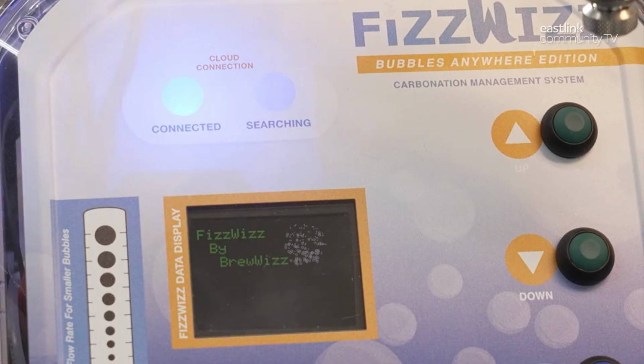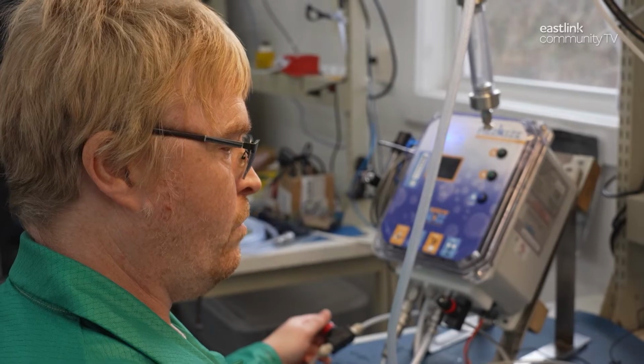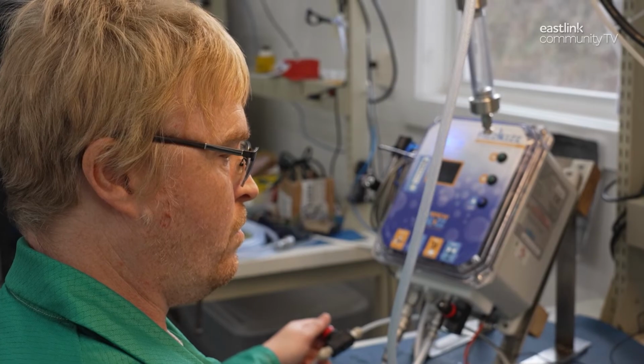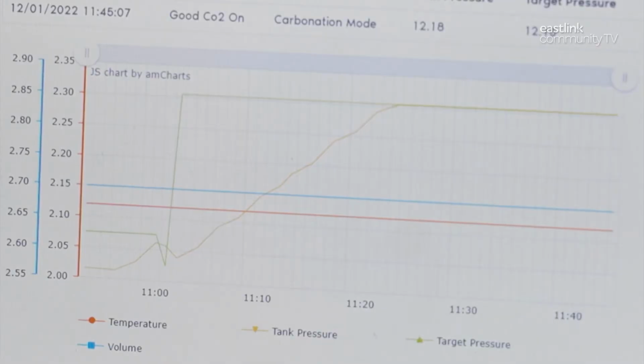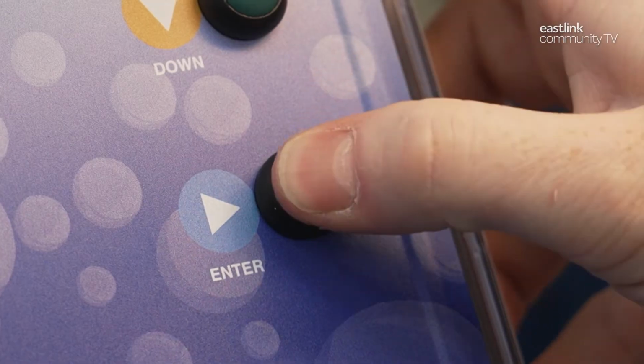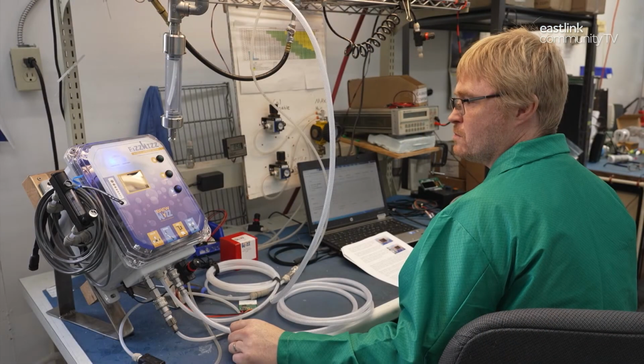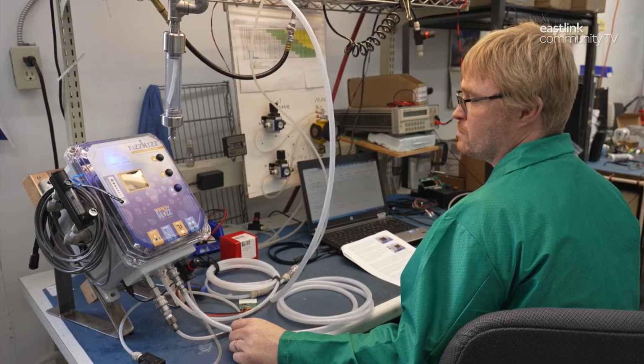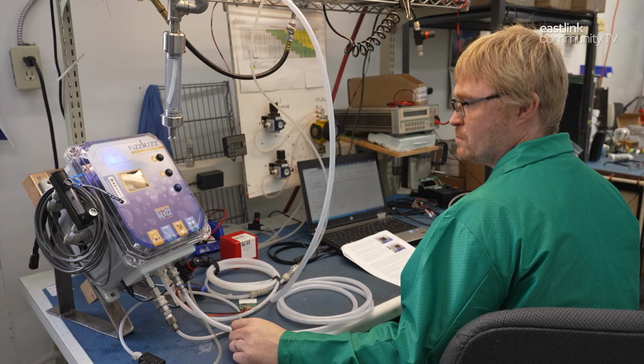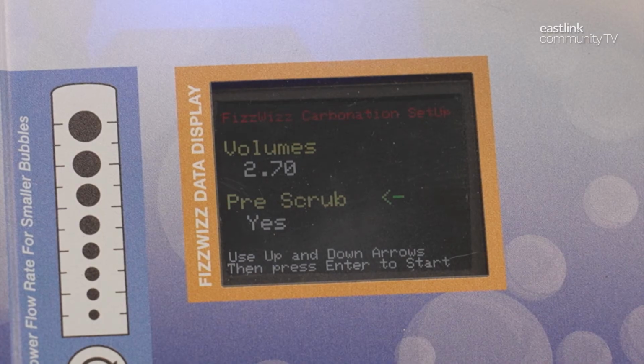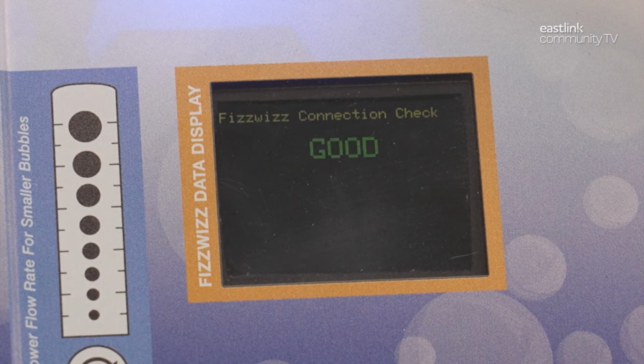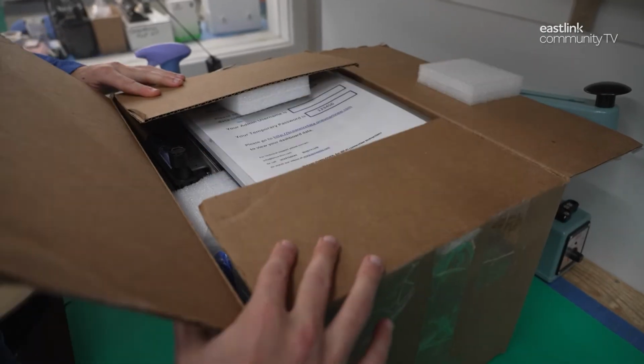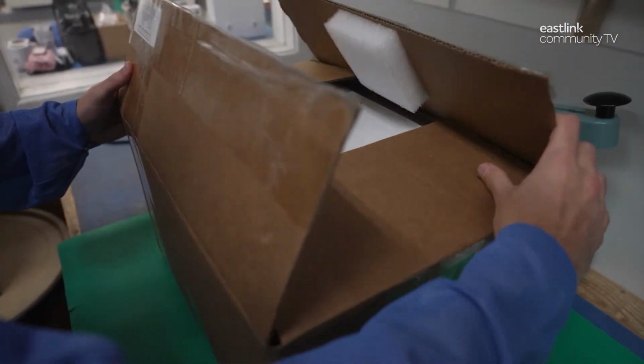After ensuring it connects to the cloud correctly, everything is tested to simulate usage on a tank. Any possible problems are corrected before setting it in test mode. All sensors are zeroed and each mode clicks through particular solenoids for 24 hours before a final factory acceptance test. Once it passes, each FizzWizz is packed for final shipment.